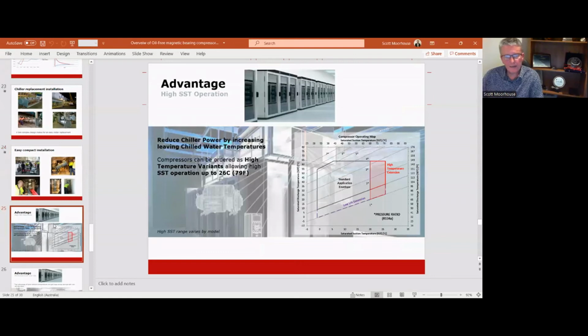The data center market has changed significantly over the past 5 and 10 years, mainly over the last 5 years, and we're seeing higher and higher SST, or leaving water temperatures. And some of the conventional compressors are struggling with these high leaving water temperatures. So magnetic bearings can withstand these high leaving water conditions quite easily, and they actually have specific compressors built for data centers or high SST operation, saturated suction temperatures.